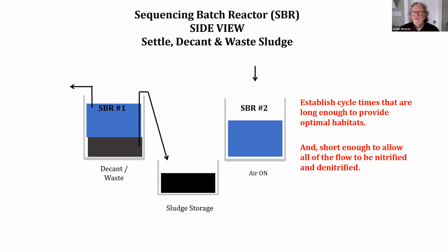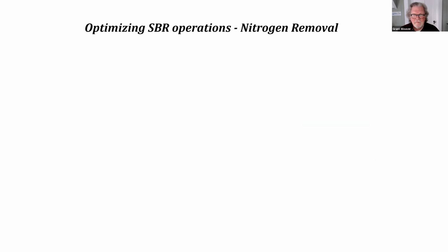In an SBR, it's so diluted out, right? You're starting with 3/4 of the tank with a low ammonia and nitrate, if you got it dialed in. That extra amount that's coming in while you're filling it up kind of gets lost. So it's real hard to do process control by measuring the ammonia and nitrate. Better to do the process control on the environmental conditions: DO, better ORP. Hopefully that makes sense.